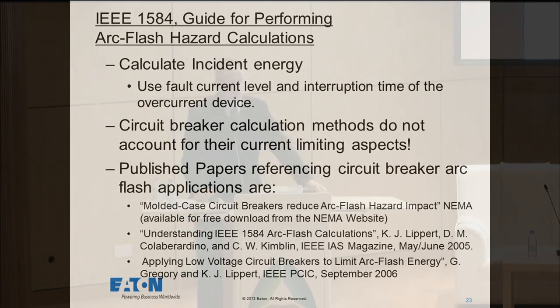One of the tools out there, the IEEE wrote a standard, 1584, and this document is being used worldwide to calculate arc flash energies. What you do is you put in a time and a current and a voltage, and it calculates the amount of energy, with calories per centimeter squared as the unit of measurement for energy. The interesting thing about this is it does not have the advantages that circuit breakers give you to help prevent against arc flash hazards. And so we've done testing beyond that to try to show these devices will help you. And there are several published papers. There was a published paper from NEMA. I co-published a paper with some other folks from Eaton, and I co-published a paper with one of my competitors that we presented at the IEEE conference for the petrochemical industry, PCIC.